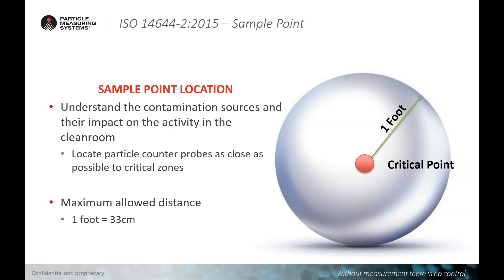The drawing on the right represents a sphere. When locating your sample probe, imagine a sphere with a one-foot radius and try to locate the probe as close as possible within that distance. In some cases this may be impossible, and if so, your inspector will expect you to provide a strong and defensible rationale proving that the position selected was the closest possible, given technical limitations or physical constraints in your filling zone.